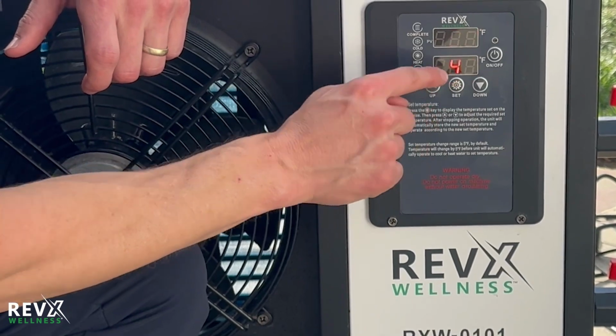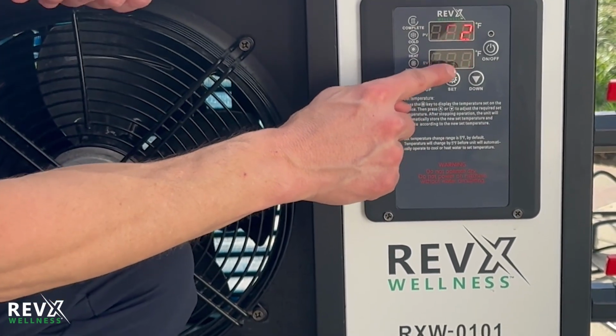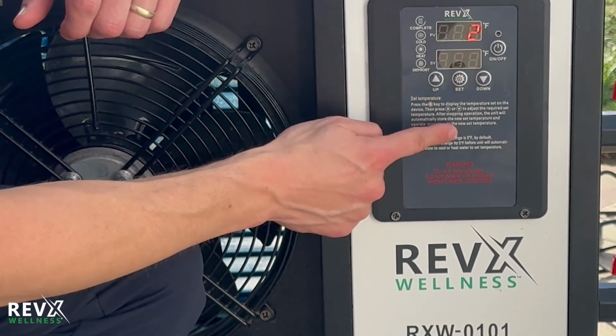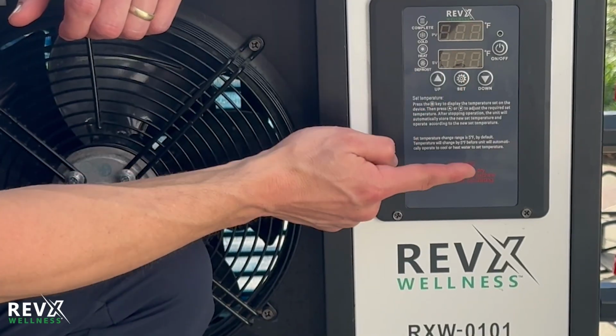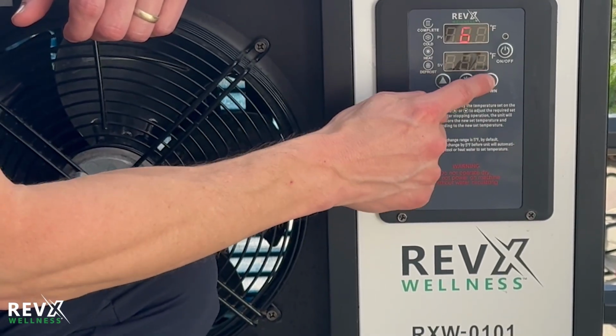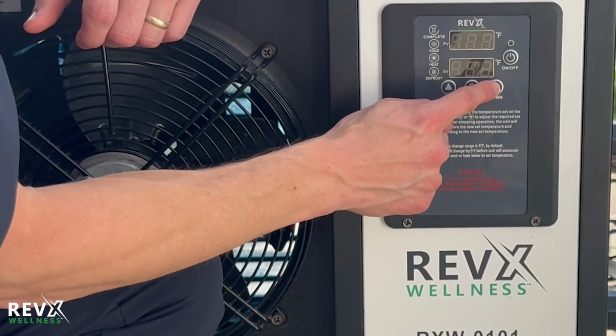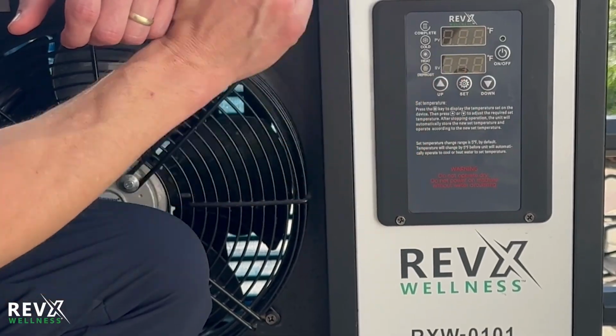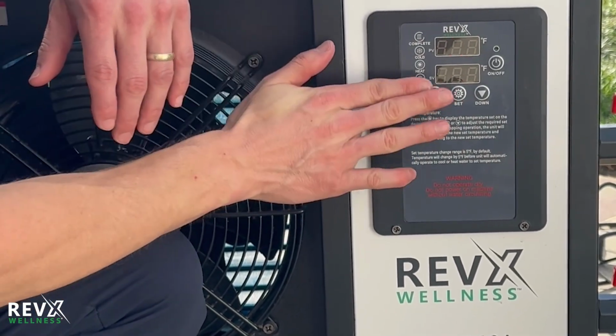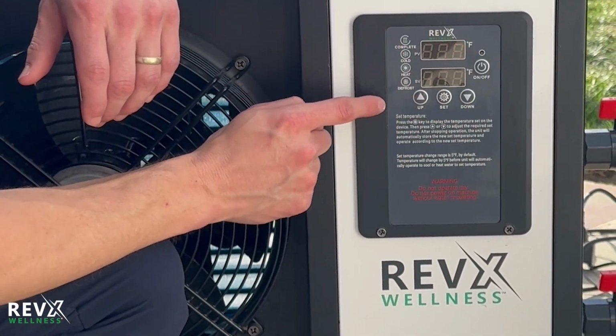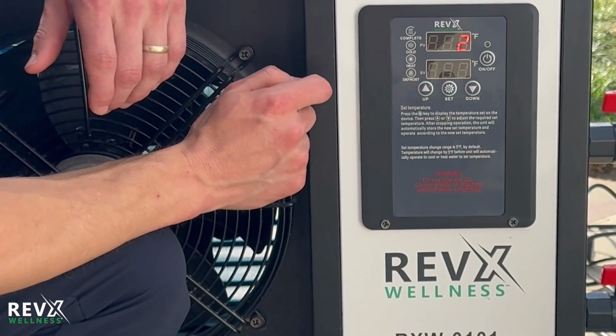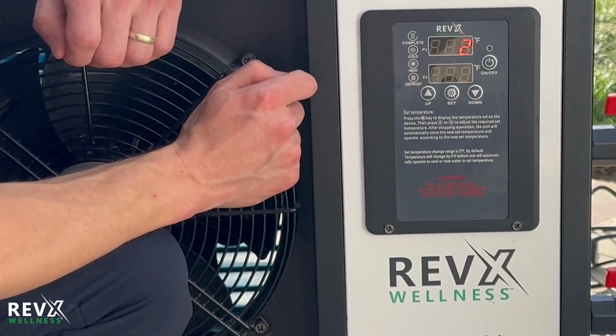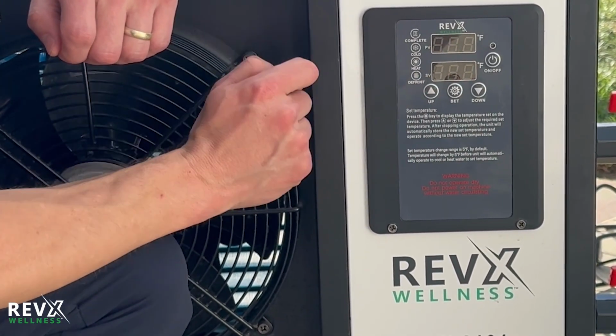And this is the set value. So this is what you want your temperature to be. To change this temperature, press the set button and then go up or down. Let's go down to 40 degrees. And this is the temperature we want. And you will see that the chiller will automatically save that. And going forward, this is going to be your set value.